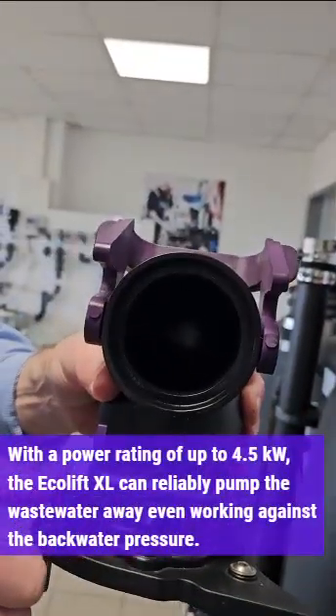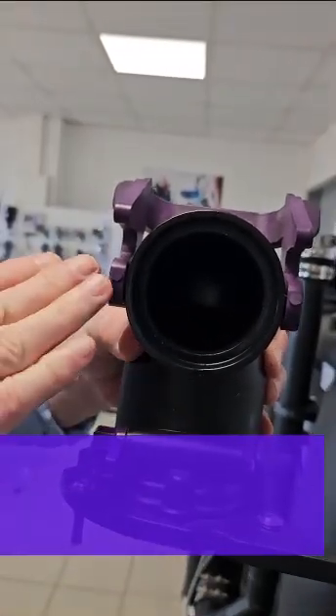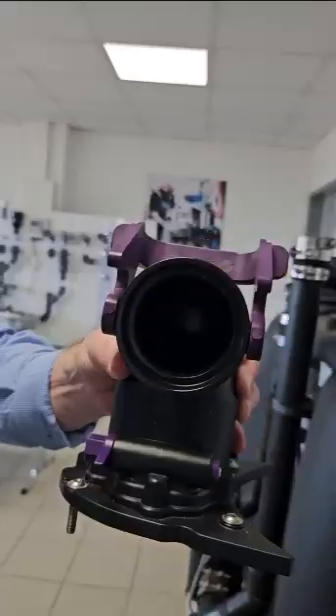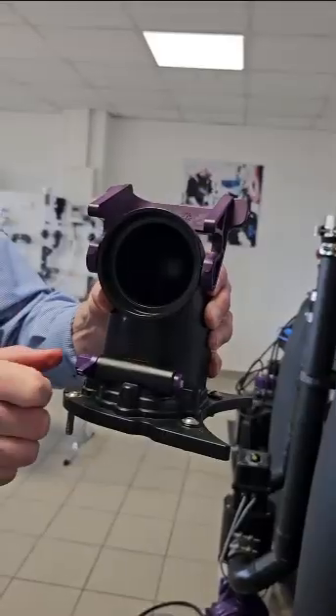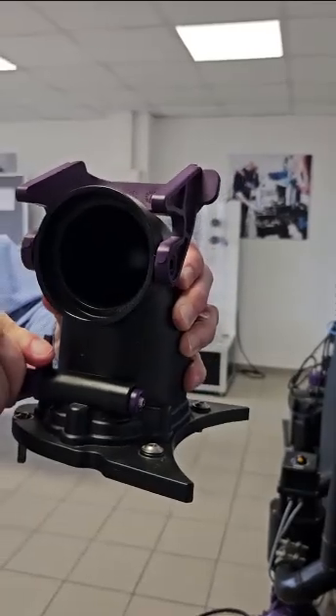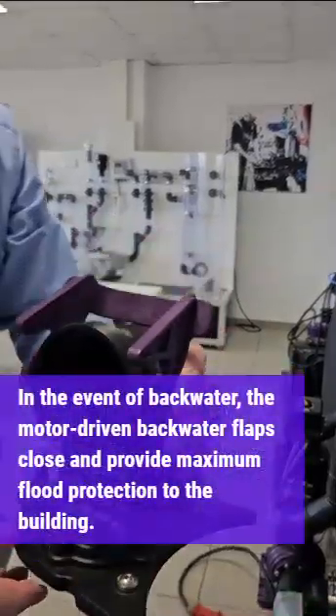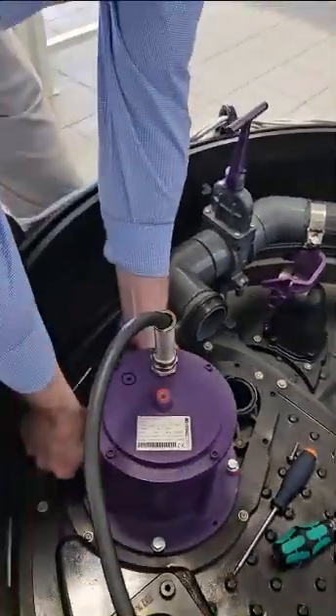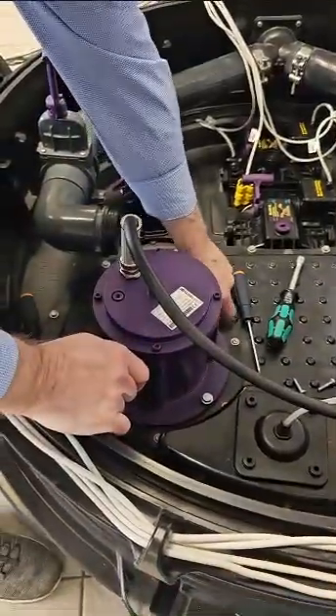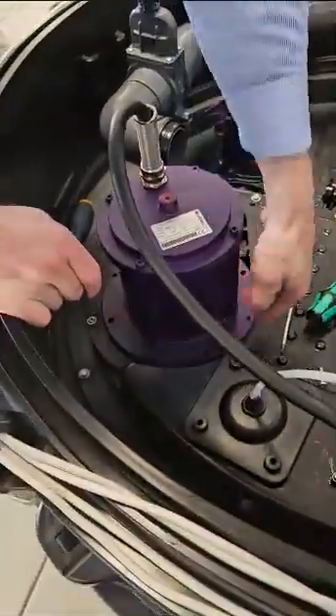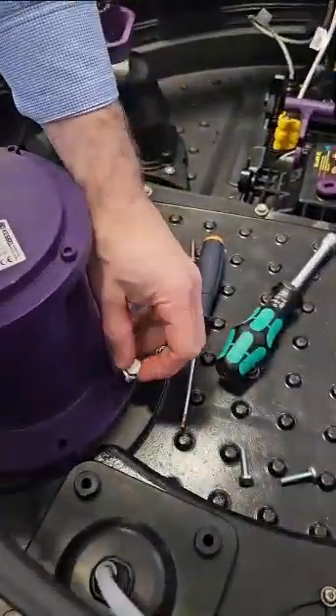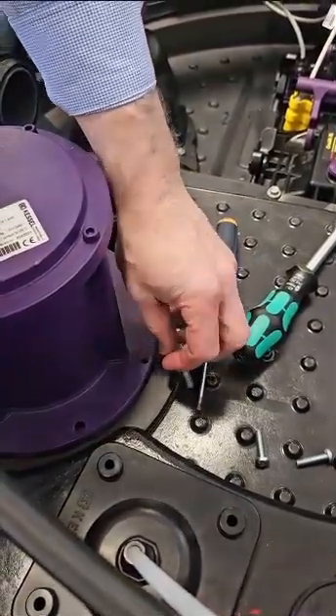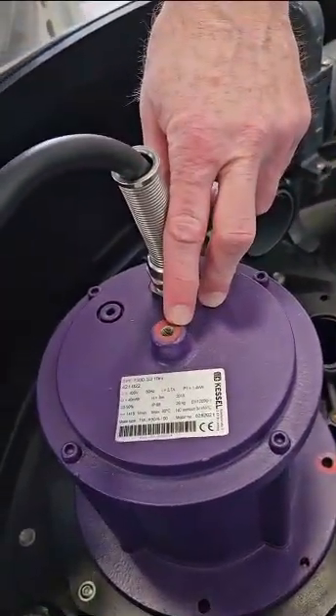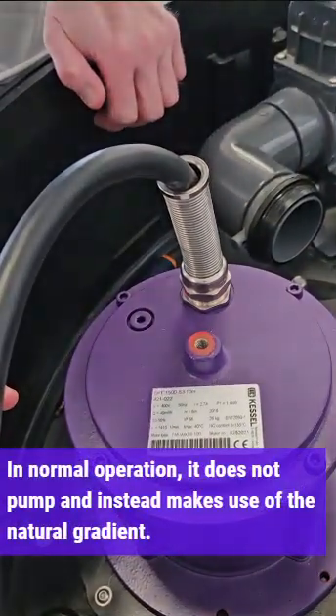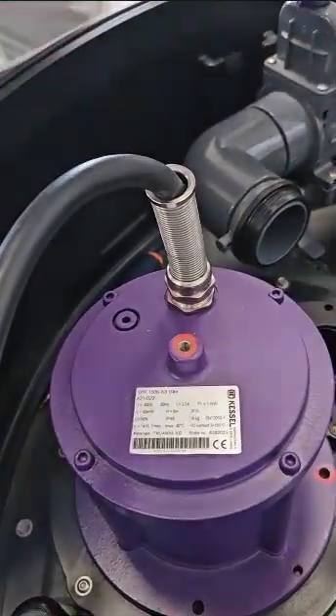Inside here we have the non-return flap that should be checked to make sure it's there and in proper working condition. This is removable. O-ring here, of course, needs to be kept in place. And inside here, there is a backwater flap that should be visually inspected to make sure it's there and in good working condition. And this is the prop lever for that flap. This should normally be in the above vertical position during normal operation. If you need to prop the flap open to drain any wastewater out of the pressure flap with a finger or a wrench, you would move this to the horizontal position. The flap is then slightly propped up, which would allow any wastewater to drain back into the tank so you don't have wastewater flooding in your working area here. But important is when it goes back into service, this lever is in the vertical position, meaning the flap is free to seal to keep the backwater pressure pipe full of water.